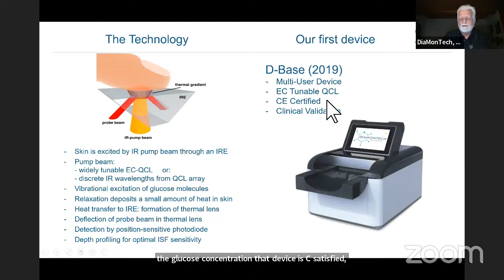Now, the technology works fine. We built a first model, a first device, which was complete in about 2019. It's shown here. It's a shoebox size multi-user device. So users can identify with an RFID chip here. The user gets his calibration curve, and this actually uses an external cavity tunable QCL, which scans the full glucose wavelength range and calculates the glucose concentration from the photothermal signal. The device is CE certified, and we have performed several clinical validations of that.